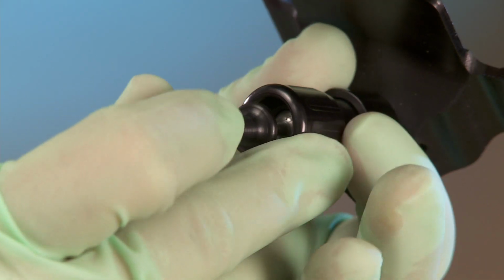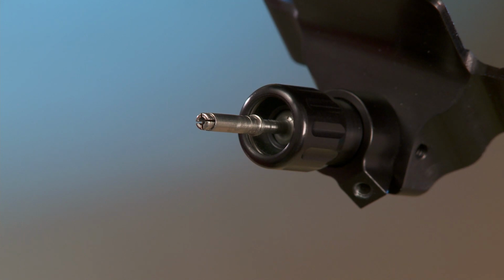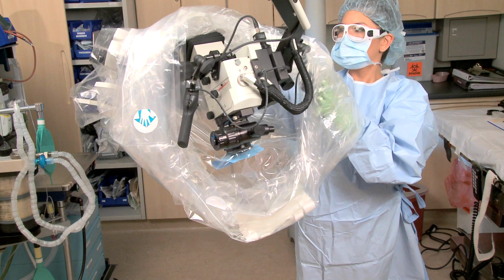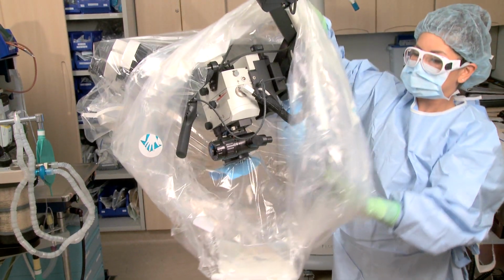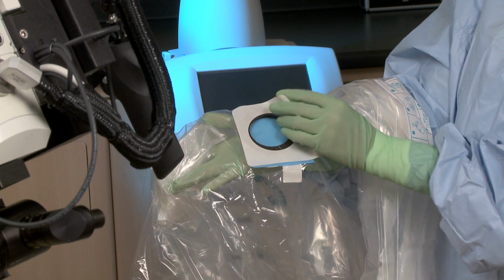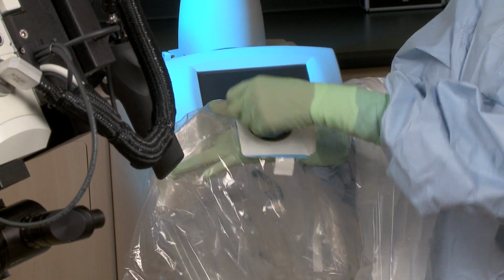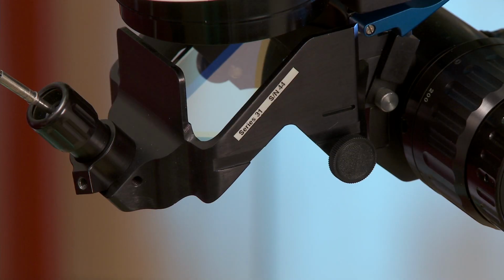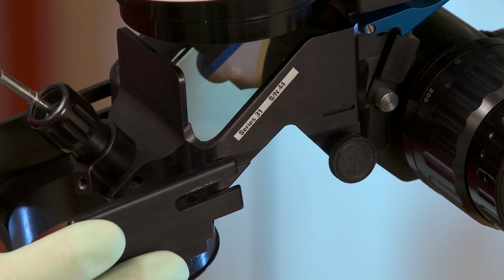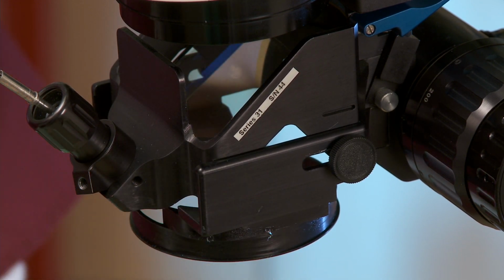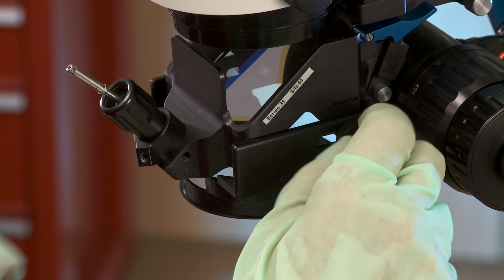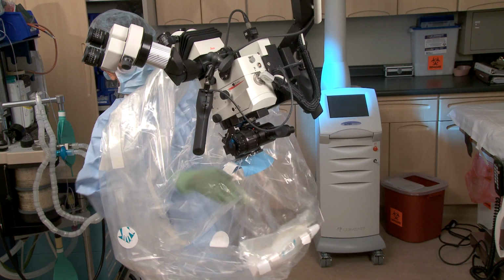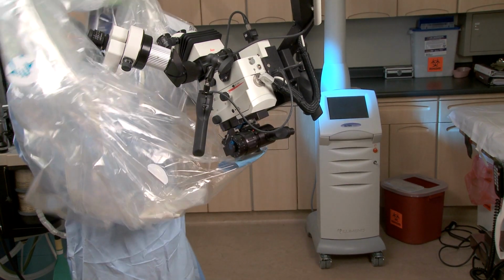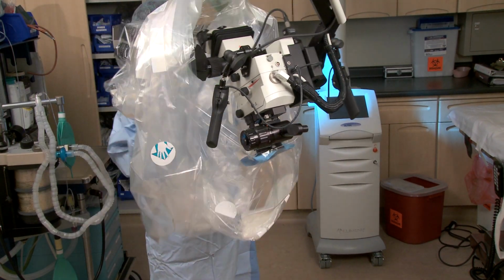The joystick has a detachable cover which can be removed after the procedure for cleaning and steam sterilization. Several manufacturers produce sterile laser microscope drapes. Instead of a cover for the objective lens, the drape has an opening for exit of the laser beam. Drape holders are included with all AccuSpot 712 series micromanipulators. The drape holder mounts around the micromanipulator aperture, and the drape attaches to the drape holder. Directions for working with drape holders are given later in this video.